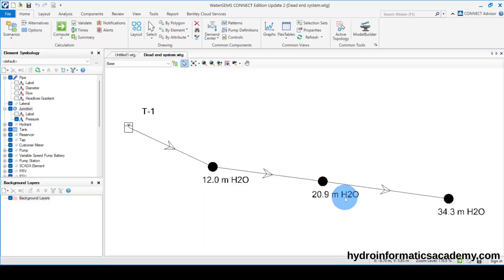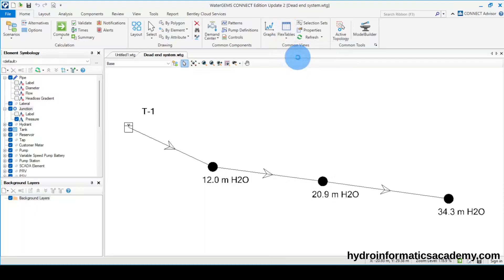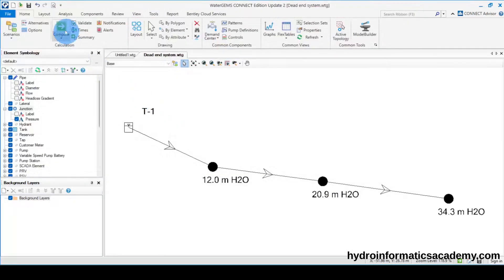Let me go straight to the flex table and select pipes. As you can tell, we are using a 1.5 inch PVC pipe. I need to reduce this pipe — the end pipe. Let me take it from 1.5 inch all the way to a 40 millimeter pipe, which is the outside diameter. The inside diameter of that pipe is around 34.9. That is the PN10. Let me run the model again and see what we have.